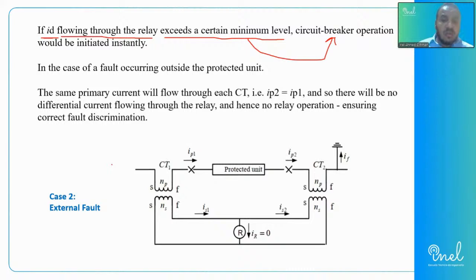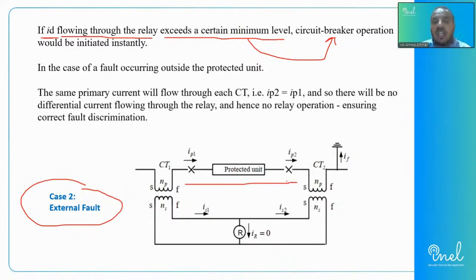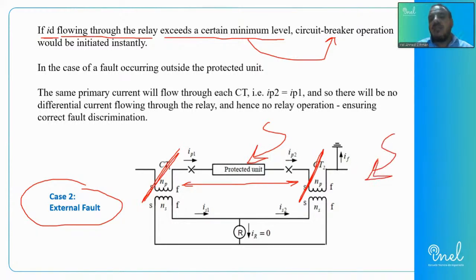On the other side, if there is an external fault, the expression of external fault depends on the protected area. Again, where is our protected area? The protected area is the area between CT1 and CT2. For any differential relay, we are protecting a certain zone which is in between CT1 and CT2. This is the protected area. Any fault internally is inside the protected area, and any fault outside is an external fault and outside the scope of the differential relay. So what will happen in case we have an external fault?